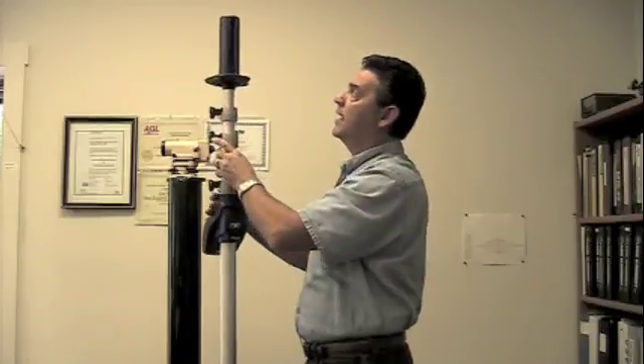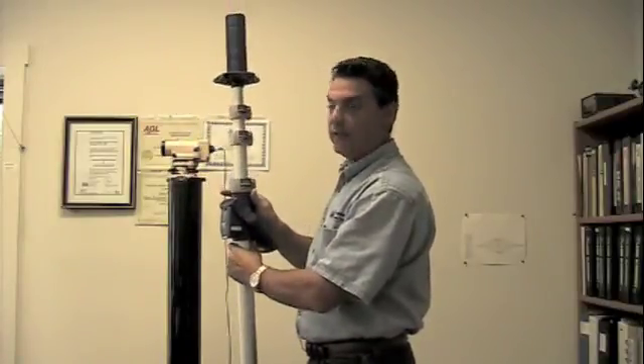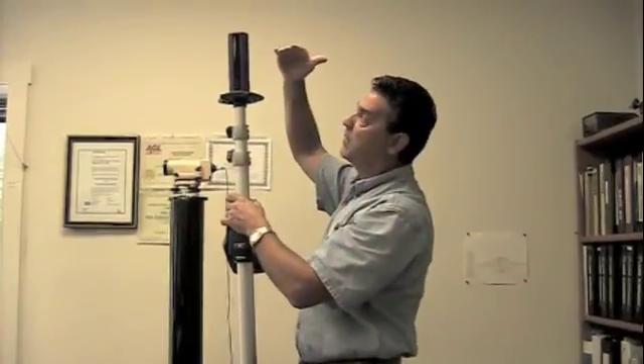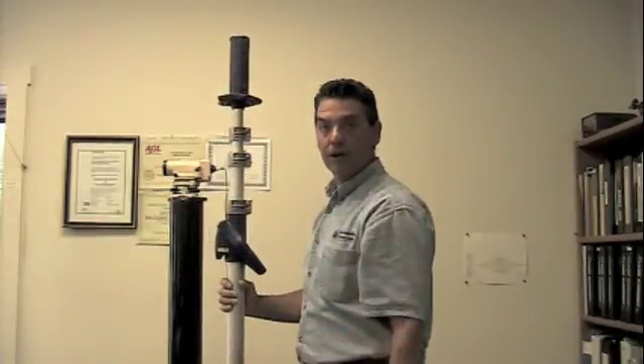The Smart Rod has a 6½ inch capture window which uses what's called linear technology. So no matter where your laser hits this receiver, it takes its measurement from that point and immediately shoots a beam to the floor, which gives you your height.